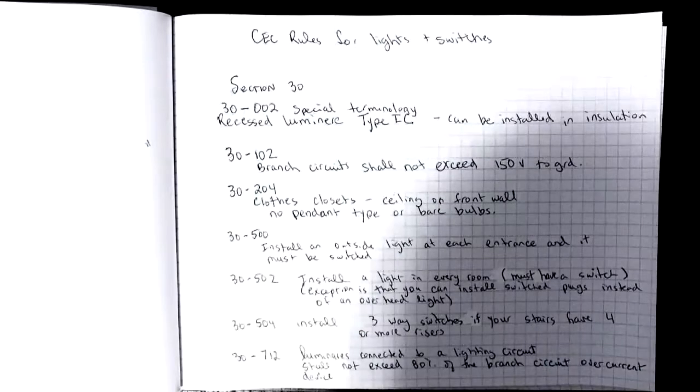Be careful though if you're switching the plugs in a bedroom that you only switch half of that receptacle, so that the other half can meet the rules of the distancing maximum distance between receptacles.